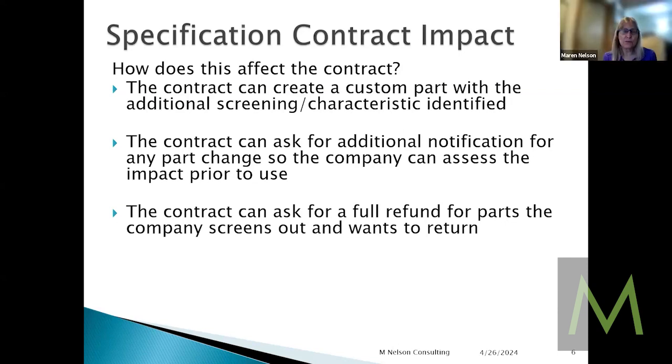And if you want to have any notifications of changes of that component, whether or not they affect the spec, then normally if they change the color, it won't affect the performance, but even if they change the color, you have to get back to the test house, say, hello there, our manufacturer has changed the color. Are you okay with it? Because it changes the critical component.